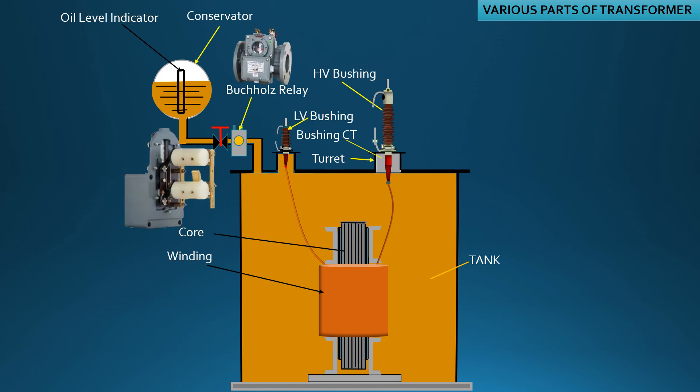This is the Buchholz relay. When incipient fault occurs at windings or core, electric flashover occurs inside oil, creating oil vaporization. The vapor comes out and reaches the Buchholz chamber and becomes trapped here.